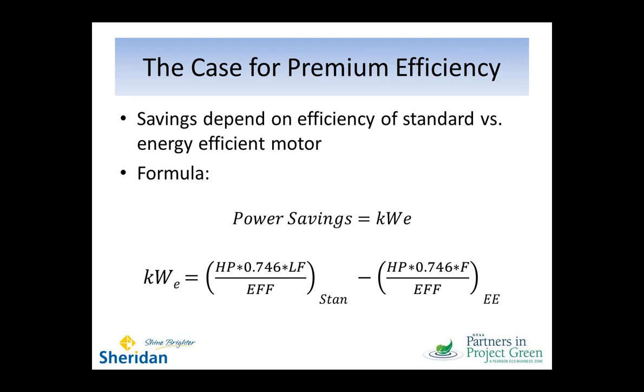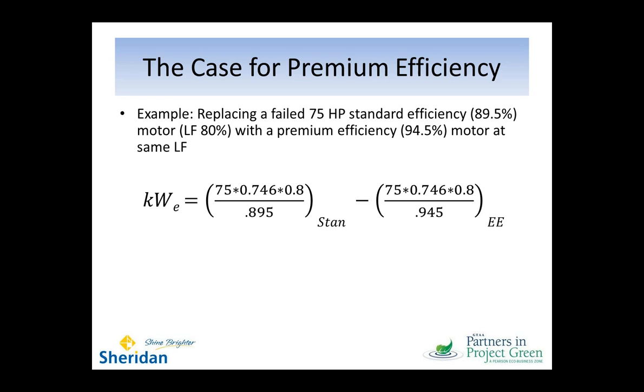And the equation inside the brackets is essentially taking the horsepower rating of the motor, times 0.746, which is the conversion to kilowatts, times a load factor, which basically tells us about how often this thing's used, and then you divide the whole thing by the efficiency. So you could imagine that a higher efficiency number in the denominator is going to make this number inside the bracket smaller. And to see that in action, let's take an example where we're replacing a failed 75 horsepower standard efficiency motor, which is 89.5% efficient. There's a load factor of 80% on this in this application. And we're going to replace it with a premium efficiency motor at 94.5%.